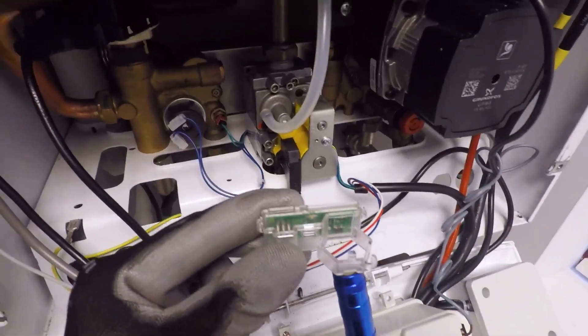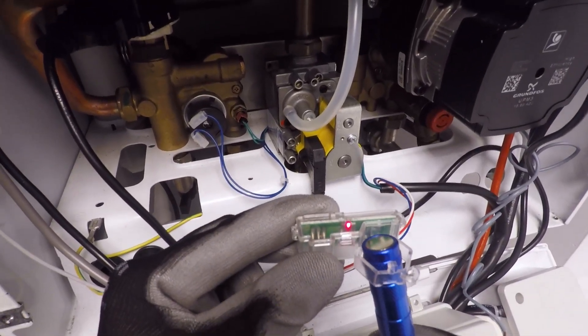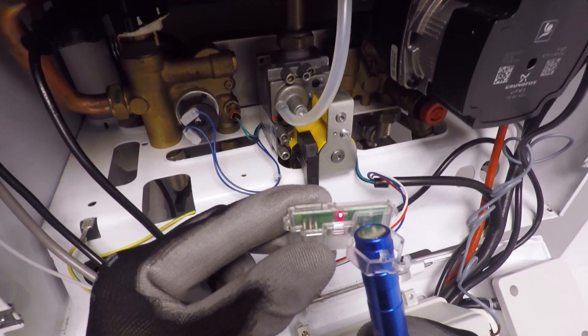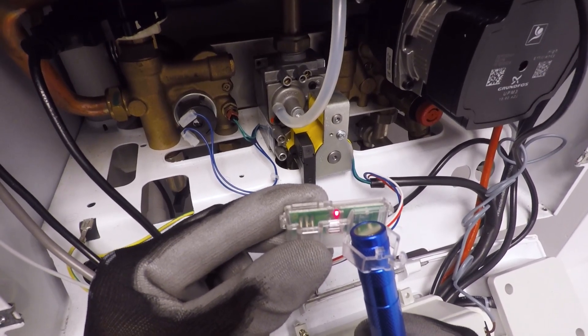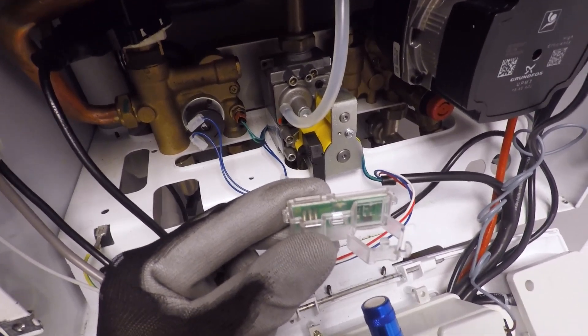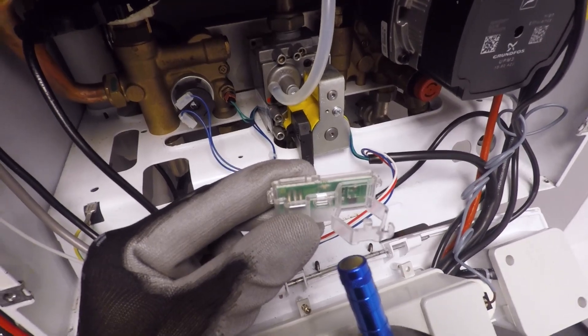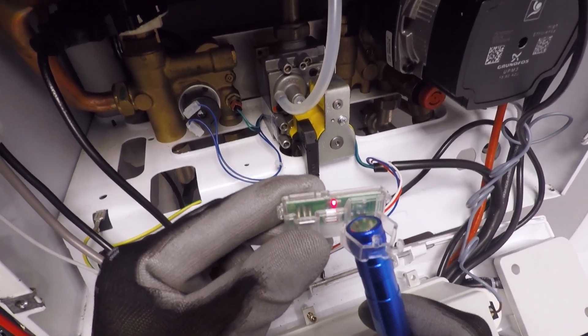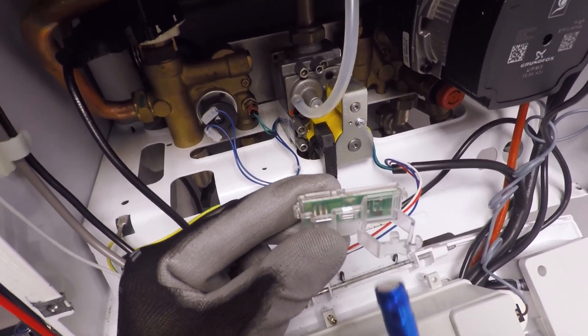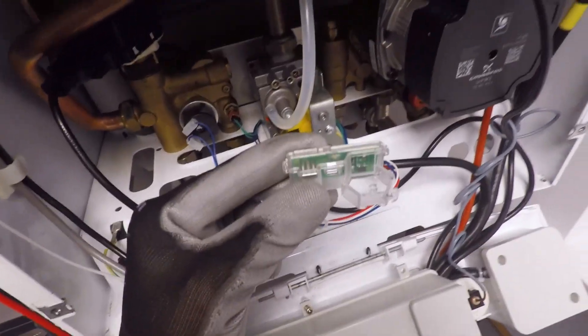So grab yourself a magnet, place it next to the little black chip there and there you go, red light on. Drop the magnet away, red light off. So as far as the boiler is concerned, hot water on, hot water off. That is the easiest way of checking them.